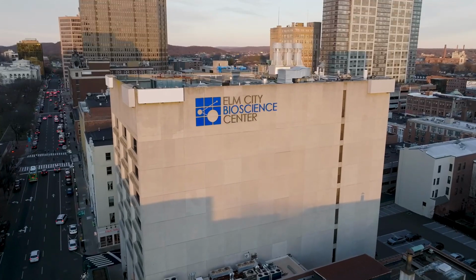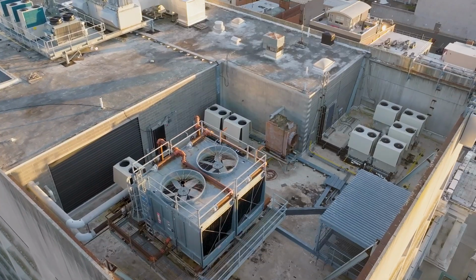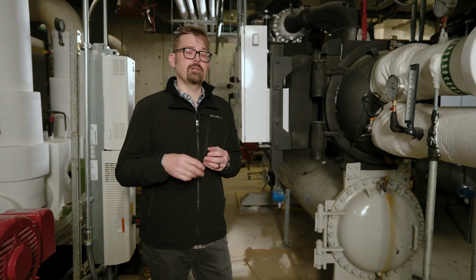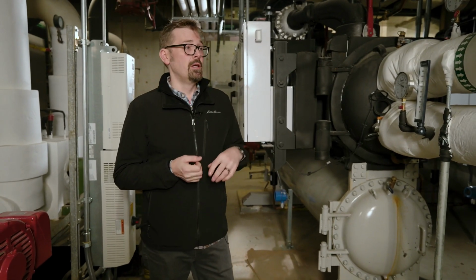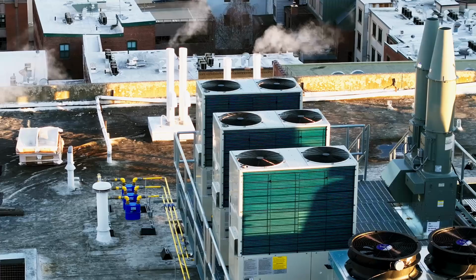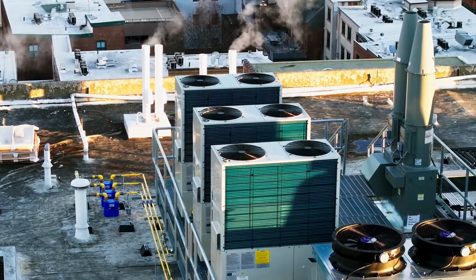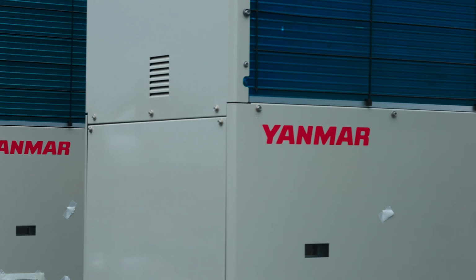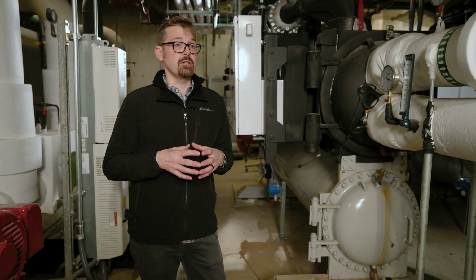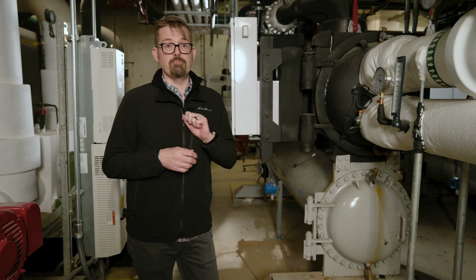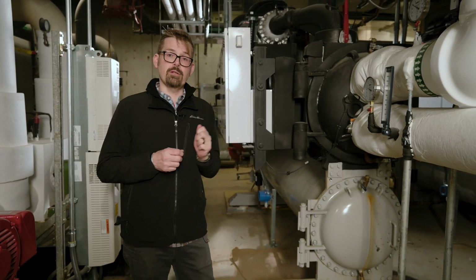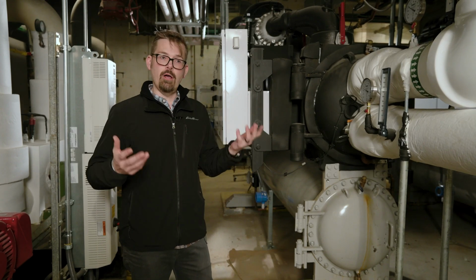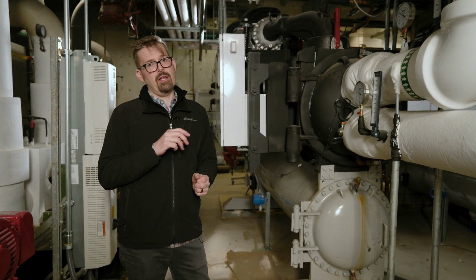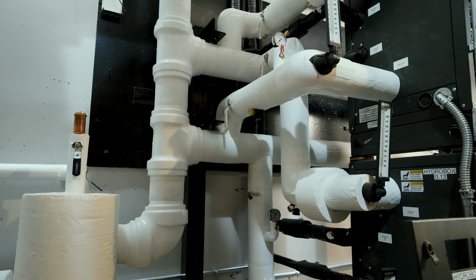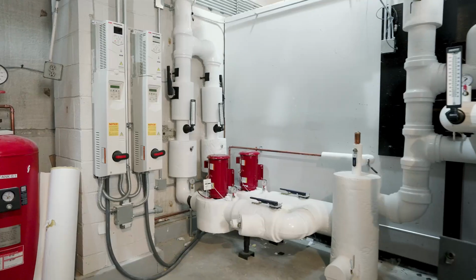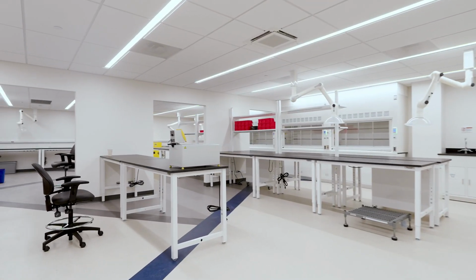In this application at 55 Church, the building had limitations with its air and its electrical. Only so much power and only so much air can be supplied by the main air handler. To overcome that, we looked at the technologies of Yanmar directly with their GHP systems, the gas-fired heat pumps. What that allows us to do in this building, instead of taking power away from the building or air from the air handler, to support different rooms on lab build-outs or in office areas, is use that GHP technology with natural gas as the main power source instead of electric or air, to support these rooms and add additional heating and cooling within the spaces.